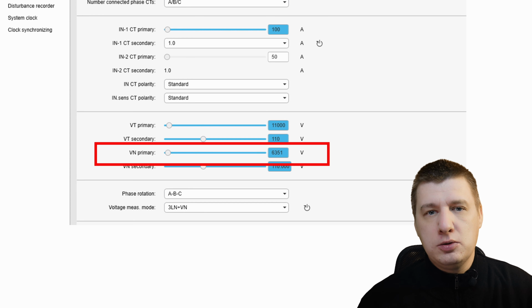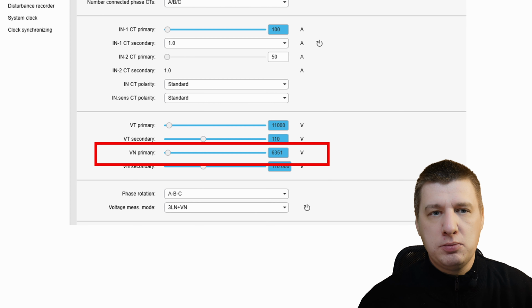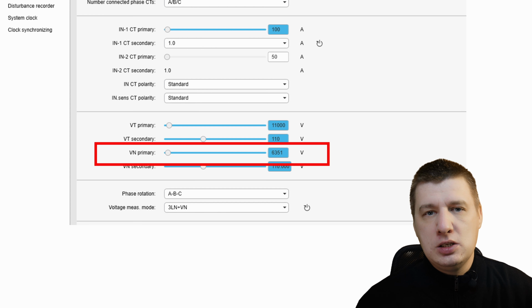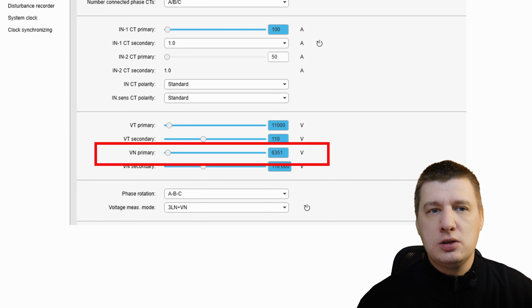We already covered how to scale your main line-to-line voltage, but today we're looking at a parameter that is often misunderstood, VN primary. If you're setting up neutral displacement protection, this is the most crucial number in your scaling menu. The VN primary is the rated primary residual voltage of your transformer. While your main VT settings cover the big system, the VN primary focuses on the neutral point displacement relative to the earth. In the P5, even if you are measuring phase to neutral, the relay's primary scaling is based on the line-to-line voltage. However, in a healthy balanced 11,000 volt system, the voltage from any phase to the ground is 6351 volts. By setting your VN primary to 6351 volts, you are telling the relay that 100%, or 1 per unit, of neutral displacement is equal to one full phase voltage. This setting is used directly by the neutral voltage displacement protection.